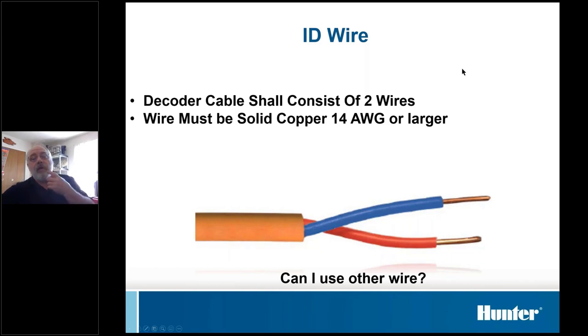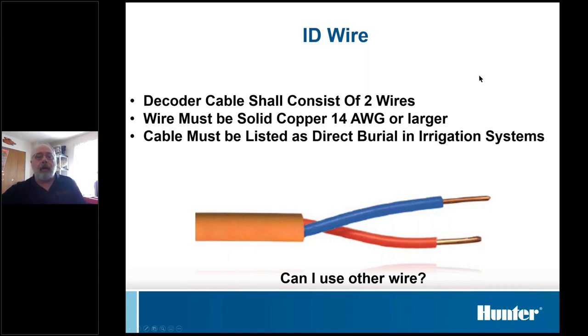If they're not solid, corrosion problems will happen faster, and we have problems with corrosion anyways. Twisted or stranded wire is notorious for having problems with corrosion. So it's got to be solid copper, it's got to be 14 gauge, and it's got to be direct bury wire.